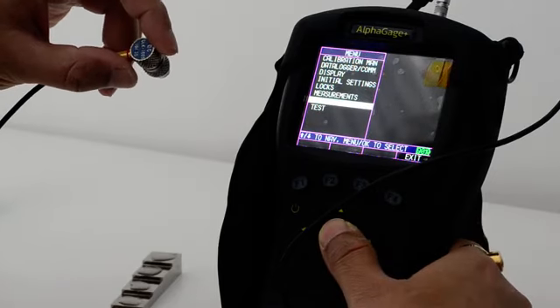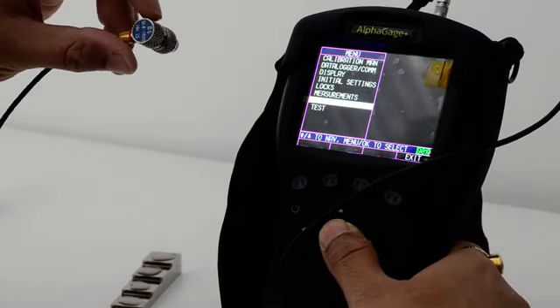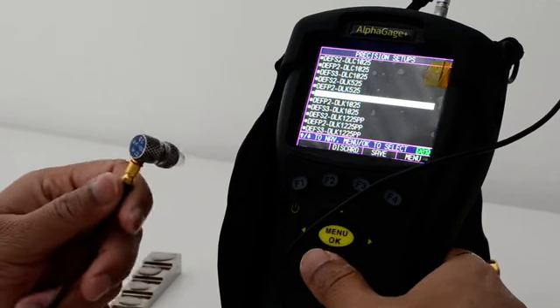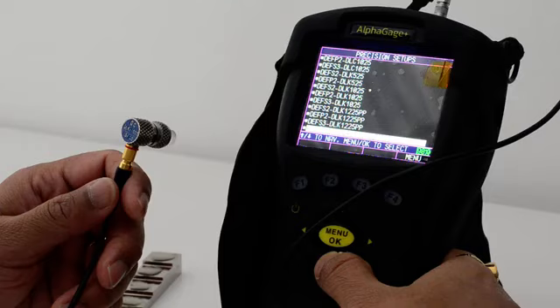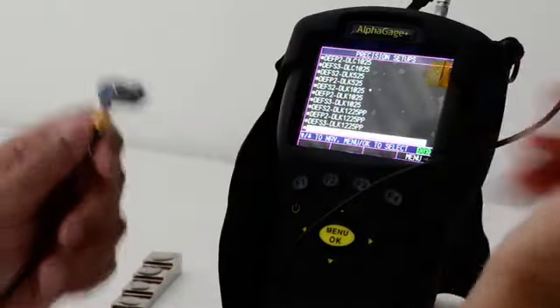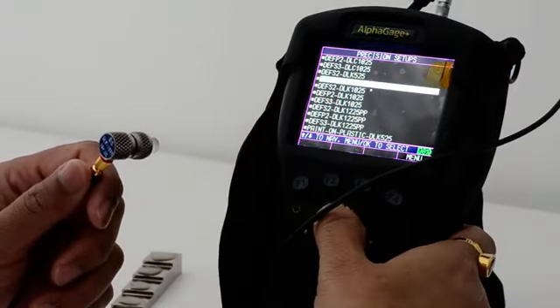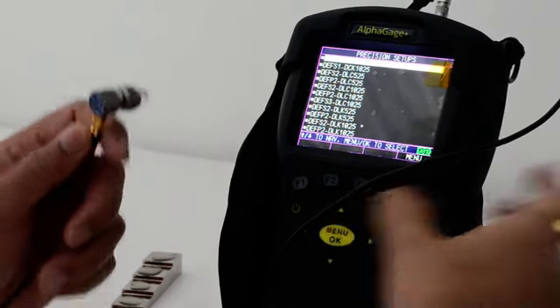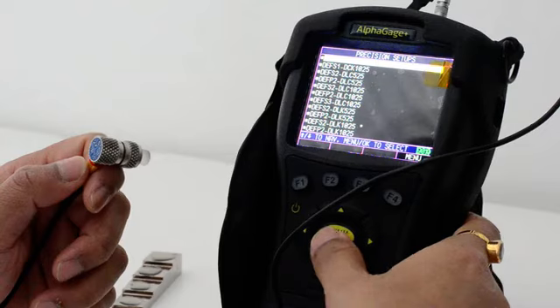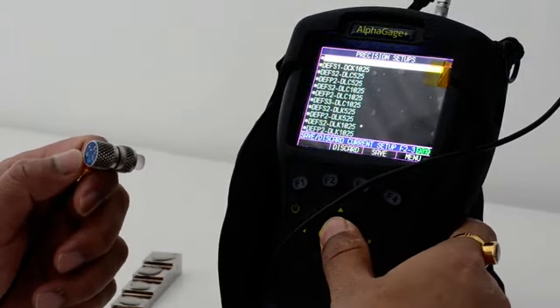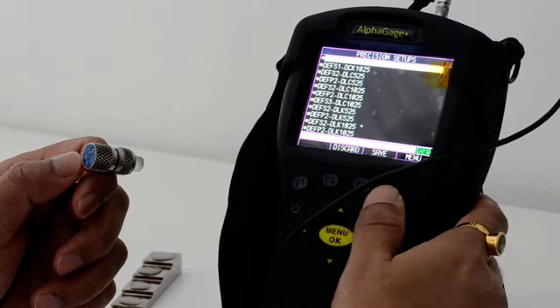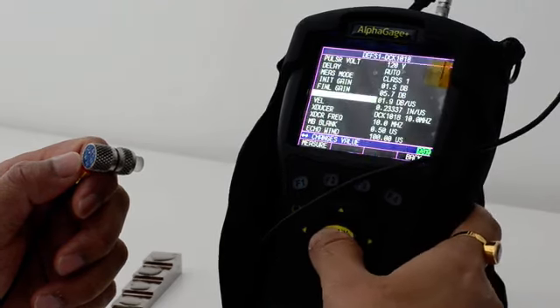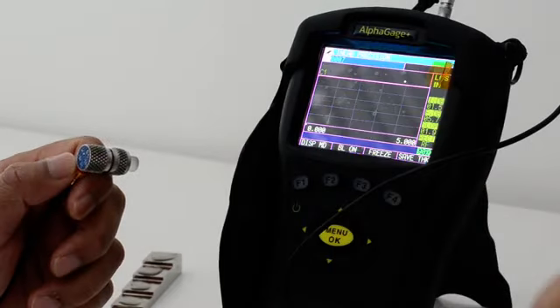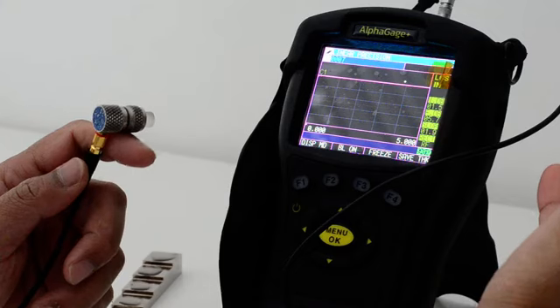And then there is setups. Setups is for the single crystal or single element transducers, like this one. All the single element transducers with which you can do a precision measurement are in this setup. So suppose you change the probe and you put in a new, different probe. Once you put the probe in, you have to go to the setup and recall the setup. Suppose I am using a different probe, which is DCK1018. Then I will go to the setup and press OK, and it will discard my previous setup. That's okay. And then I'll press measure, and I am in a setup for the new probe, DCK1018.